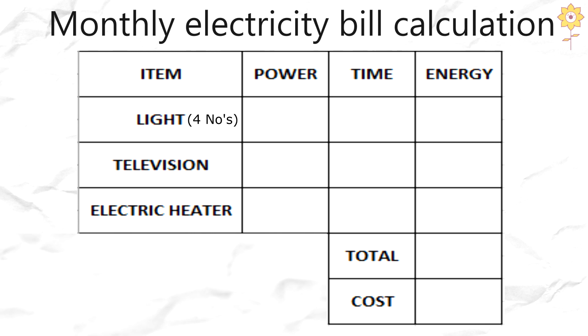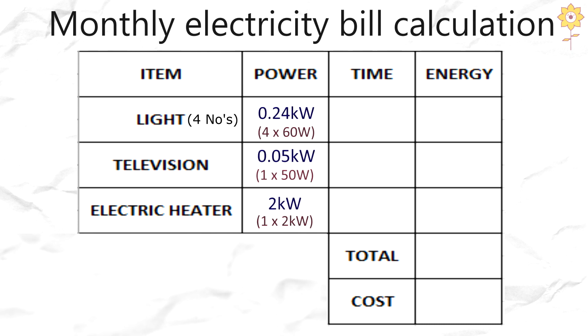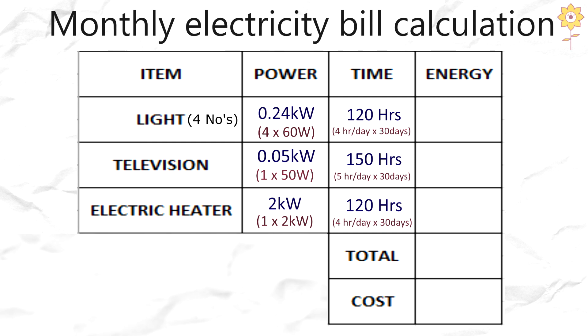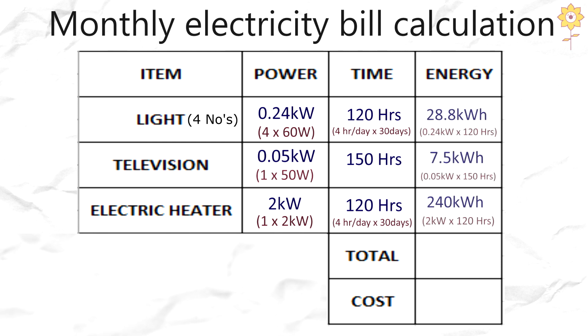To figure out monthly electricity usage, first make a table of all electrical items in the building and record their power ratings — making sure each is in kilowatts. Then record how many hours per month each item will be switched on. Use the formula energy equals power multiplied by time for each device, then add up all the values in the energy column to get your total monthly kilowatt hour usage.